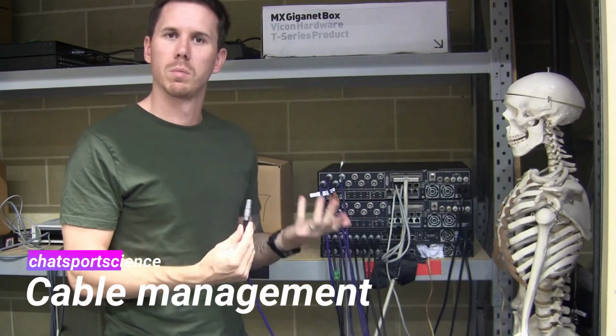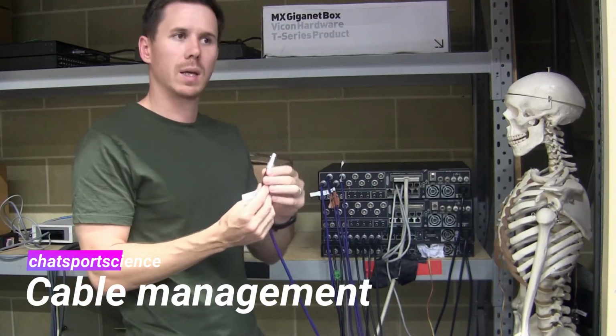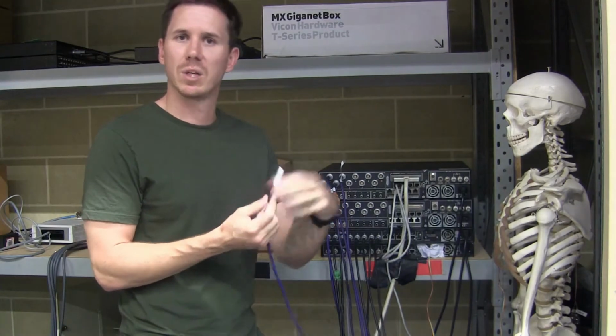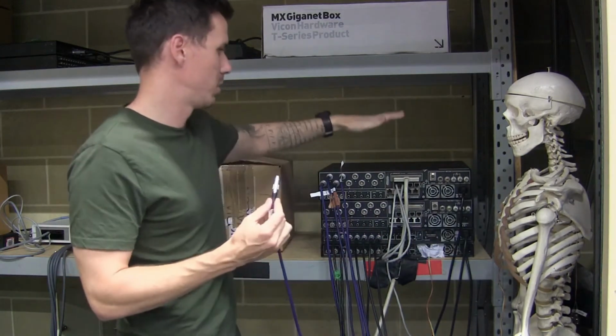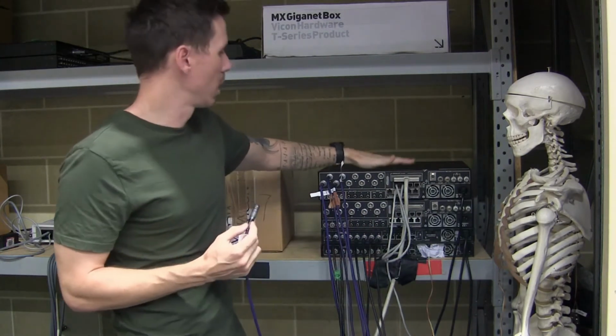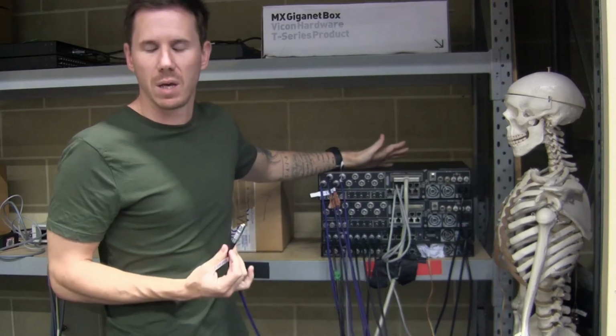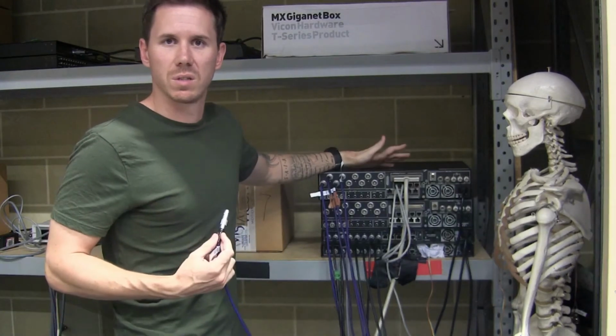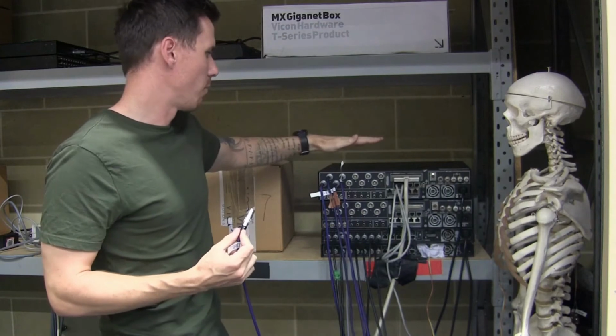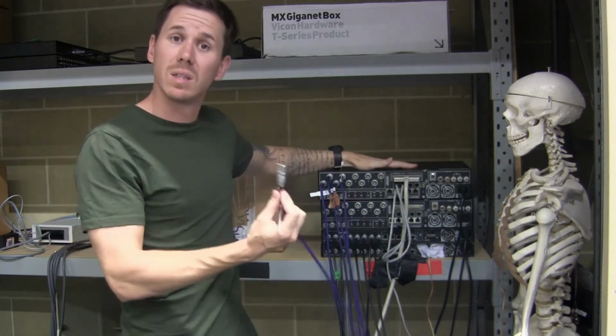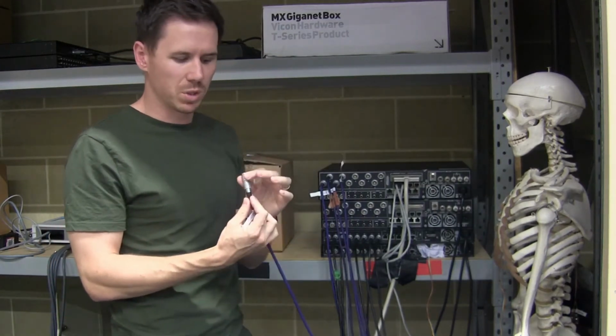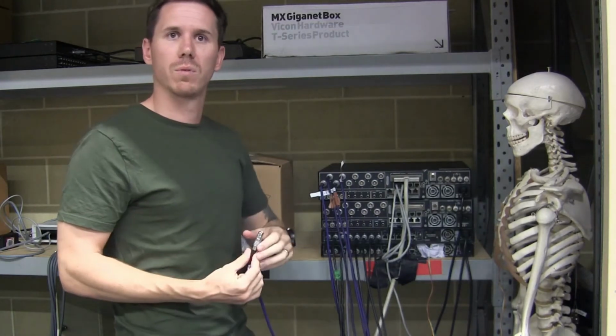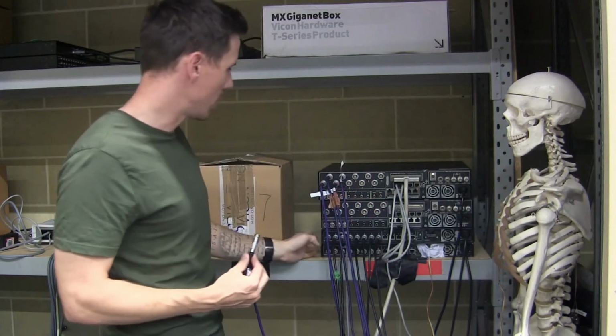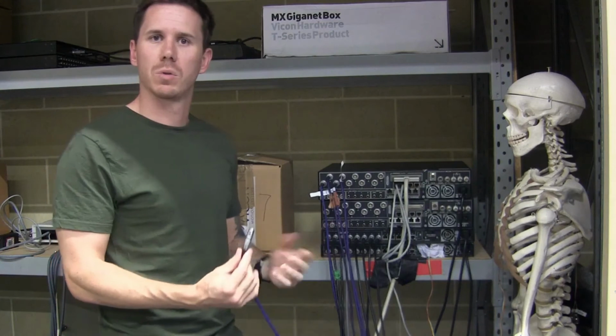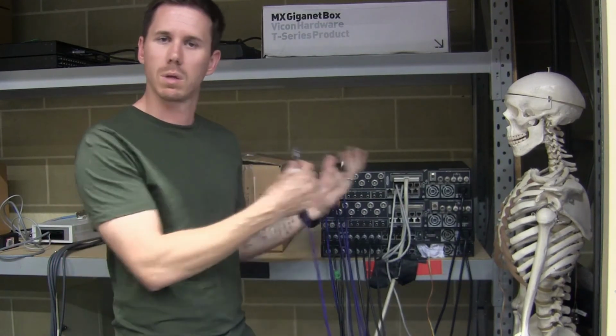So the way I recommend you do it is you take each cable that you're going to be plugging into each camera, and you plug it first into the GigaNet box. These GigaNet boxes you should have as standard when you purchase a Vicon system. You have one GigaNet box that takes the T-series camera cable, which is just a little bit wider than, for example, the MX series that we have down here at the bottom. So you just have to make sure that you plug the corresponding cable into the correct box.